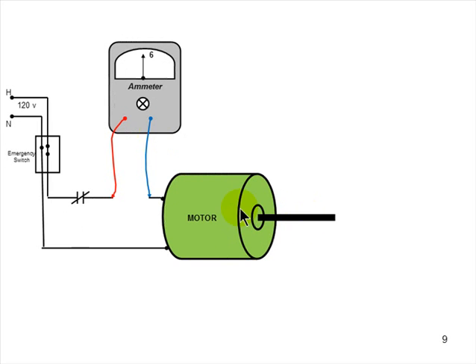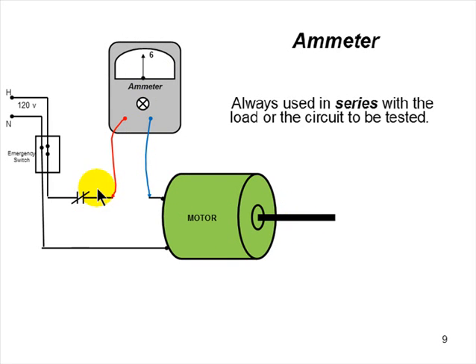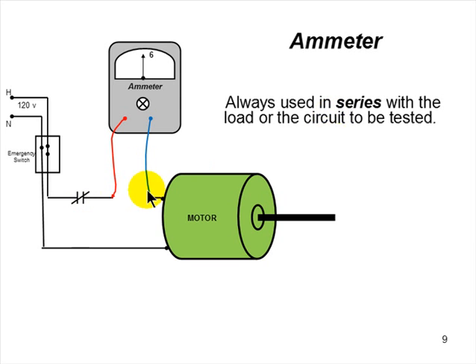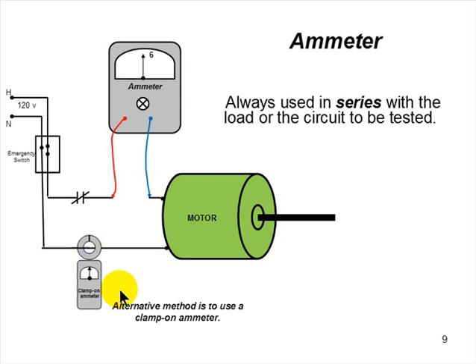How's an ammeter connected? Well, an ammeter's in series, isn't it? Always in series. You can't read amps if you're in parallel with the load. You have to be in series with the load. Now, if this is a 6 amp motor, I ain't standing there holding on to these two things with my hands. I'm either using alligator clips or I have this wonderful device called a clamp-on ammeter, which simply has to be tangent, perpendicular, whatever, to the flow of current. And it reads the intensity of the magnetic field. Ammeters for the test, always in series.